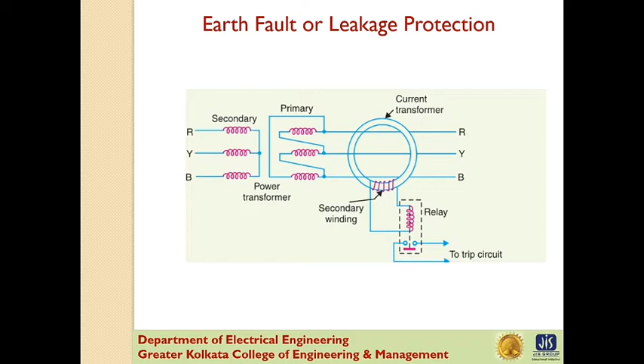Now, when a fault occurs, the vector sum of the three-phase currents is no longer 0. The resultant current sets up fluxes in the core of the CT, which induce EMF in the secondary winding. This energizes the relay to trip the circuit breaker and disconnect the faulty transformer from the system.